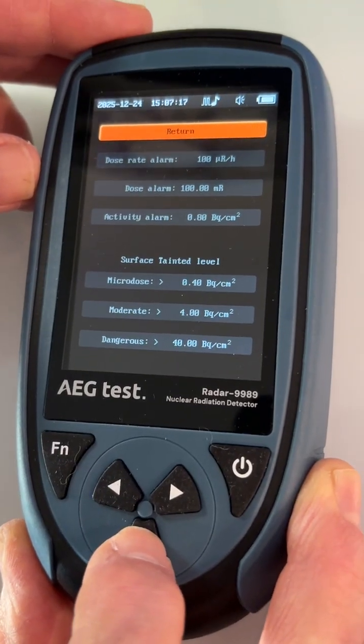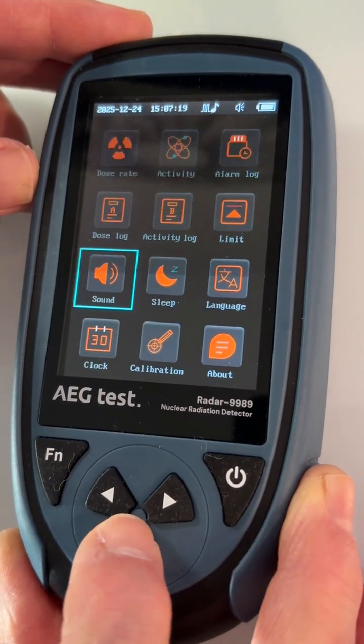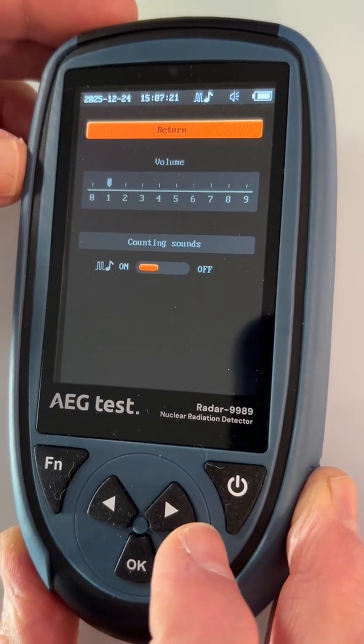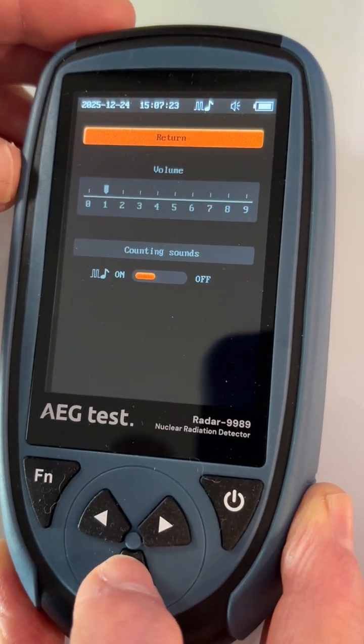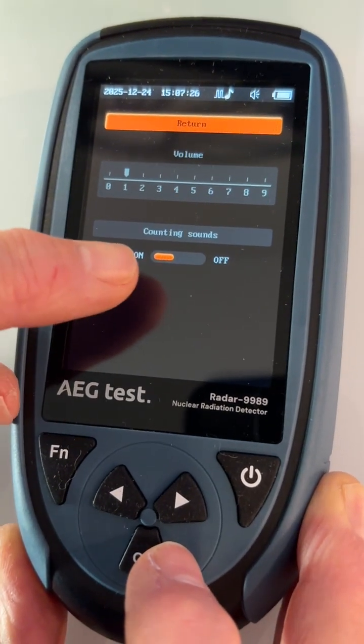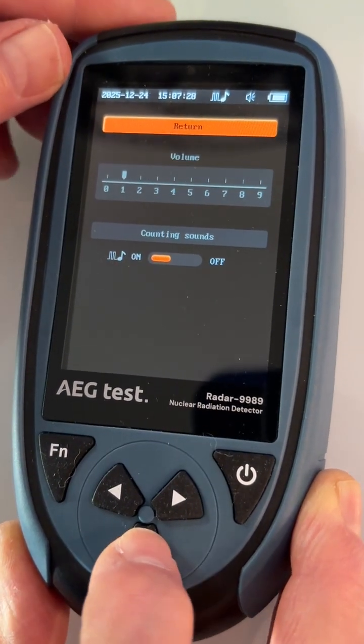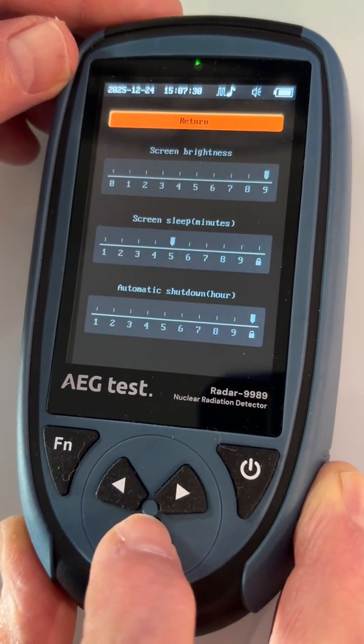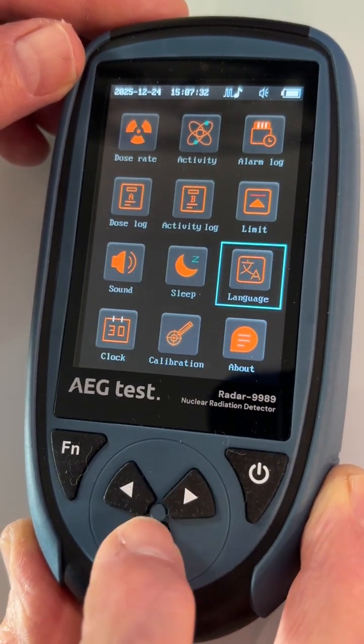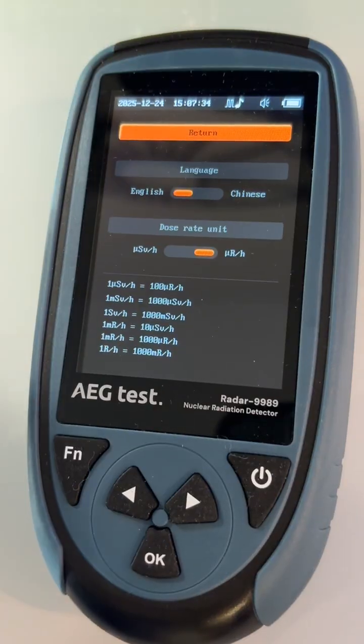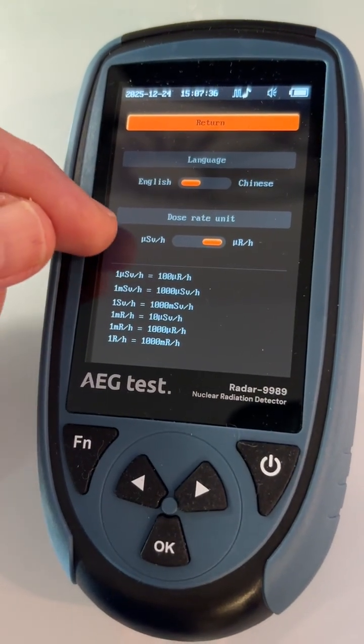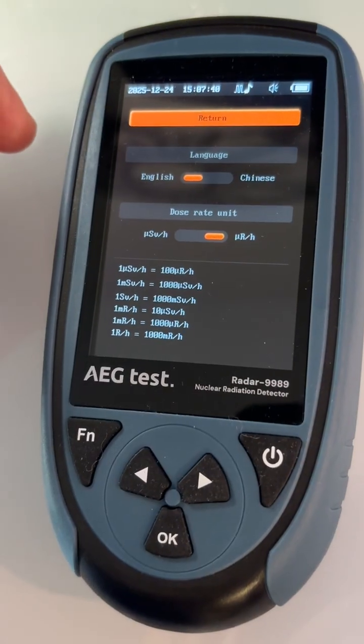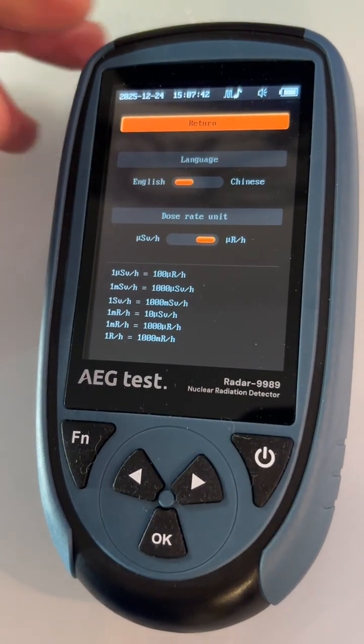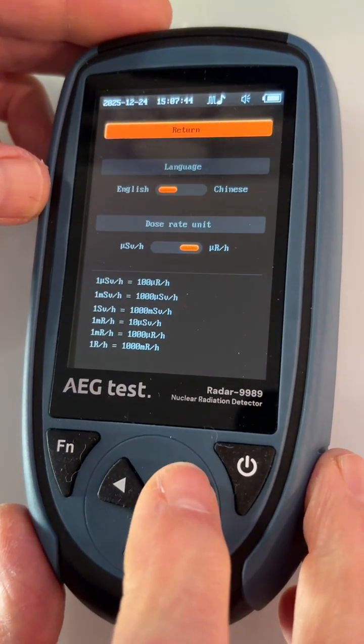Limits, you can set the limits in the device, okay? Sound, I usually leave the sound off. I just have it on for this review, but there's where you would turn it off, or turn the count rate or count sounds off or on. Sleep mode if you so choose to use it. Language setting, this is kind of important. On the language setting, you can switch from microsieverts to microroentgen. I have it set to microroentgen right now, but that's where you would do it within the language settings. So just keep that in mind.